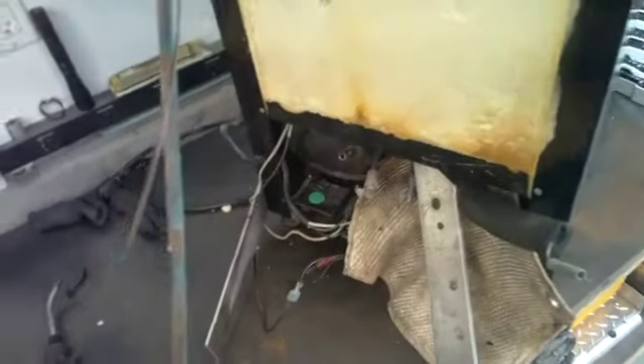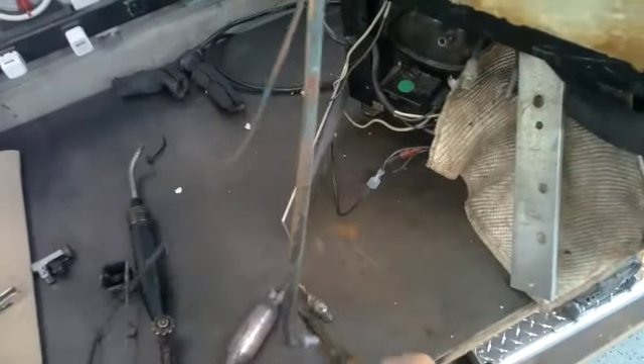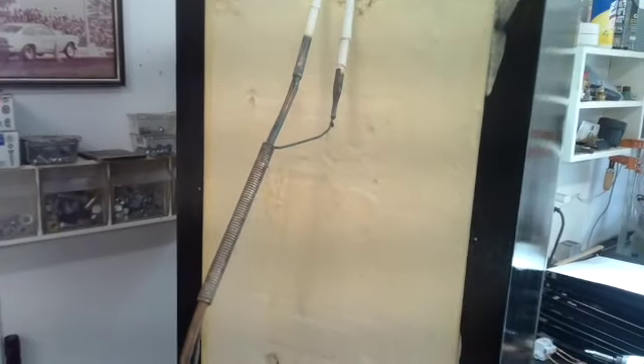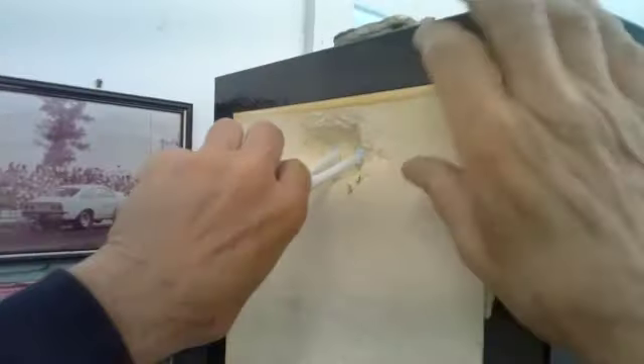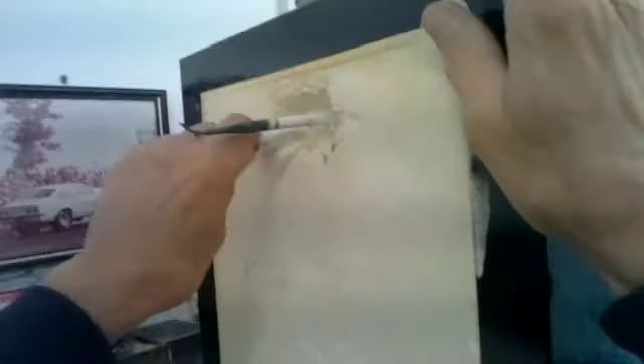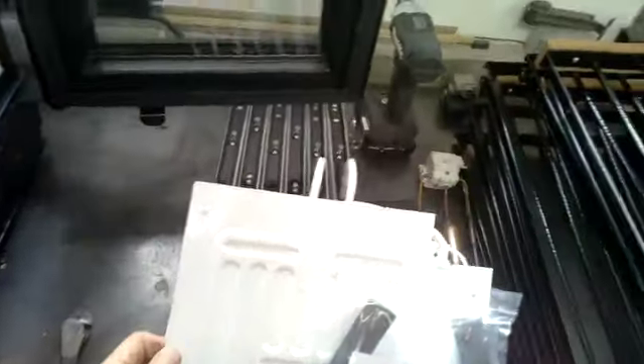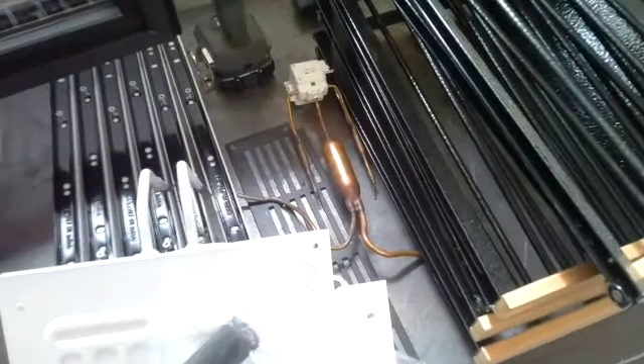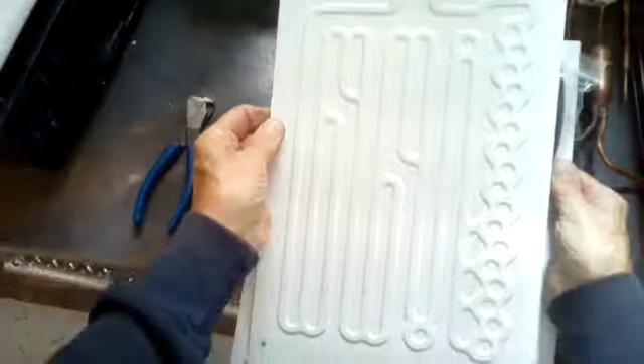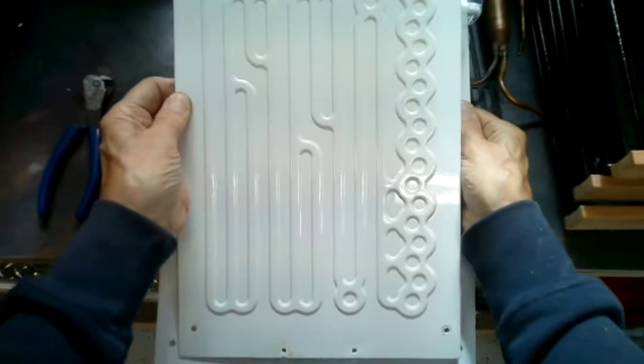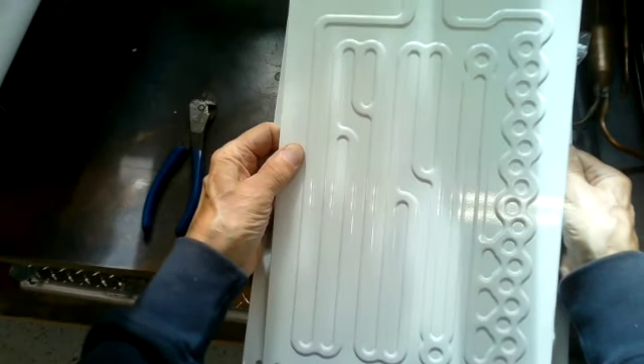Okay, I unsweat the suction line, and I also pulled out the dryer. So now we just need to pull the evaporator through and fit the new evaporator into the slots. Okay, that's disconnected. Just pull this through. All right, so there's the old evaporator. Let's see how this compares with the U-line evaporator. Yeah, it's a little wider. Holes are in a different spot, but the slots on the bottom for the feeler bulb are the same.